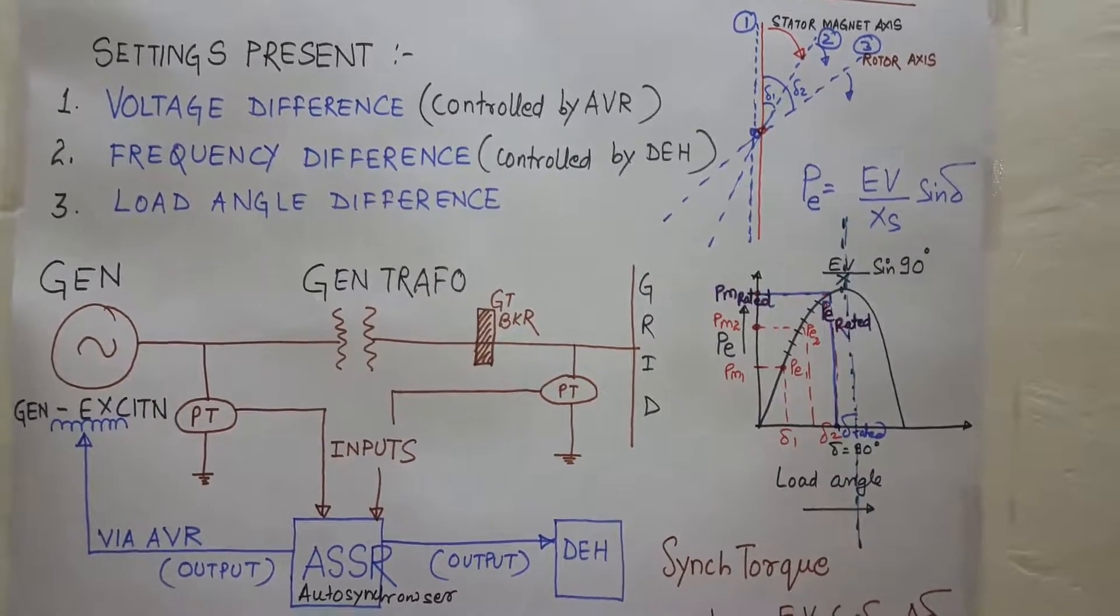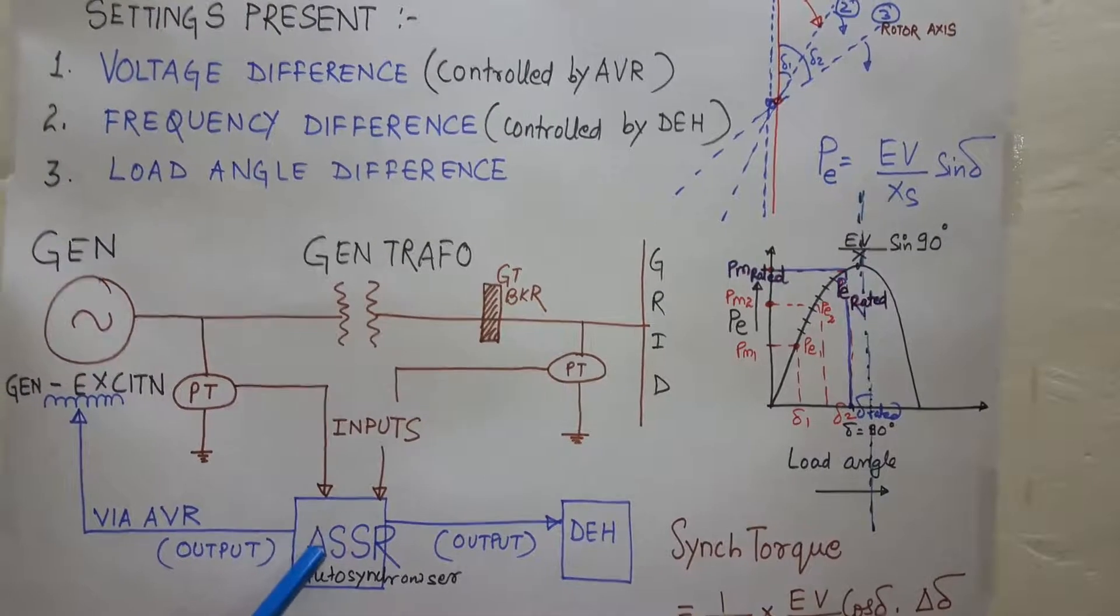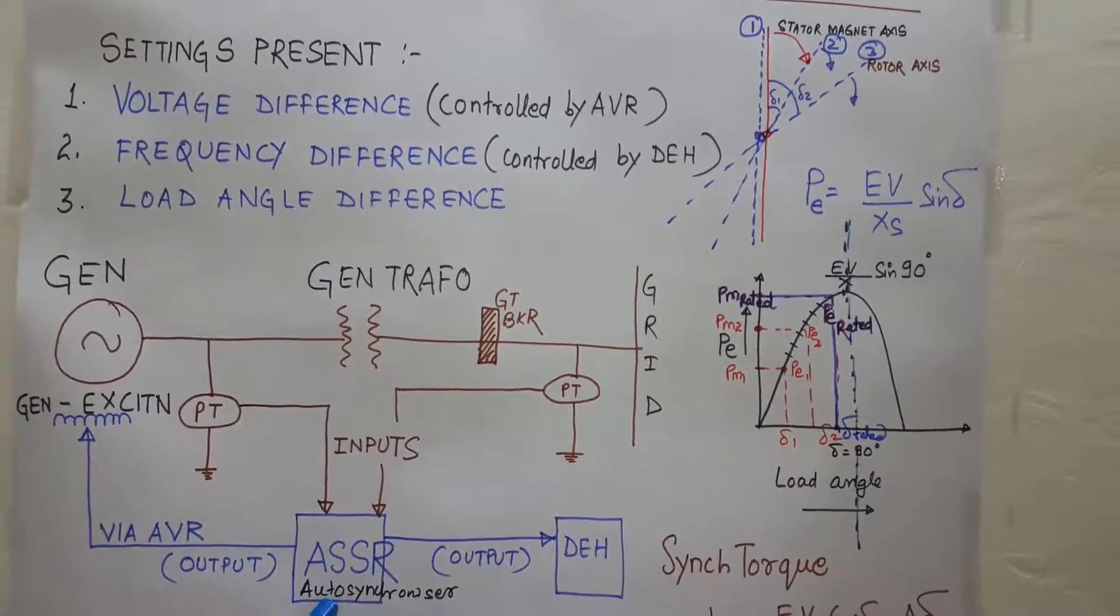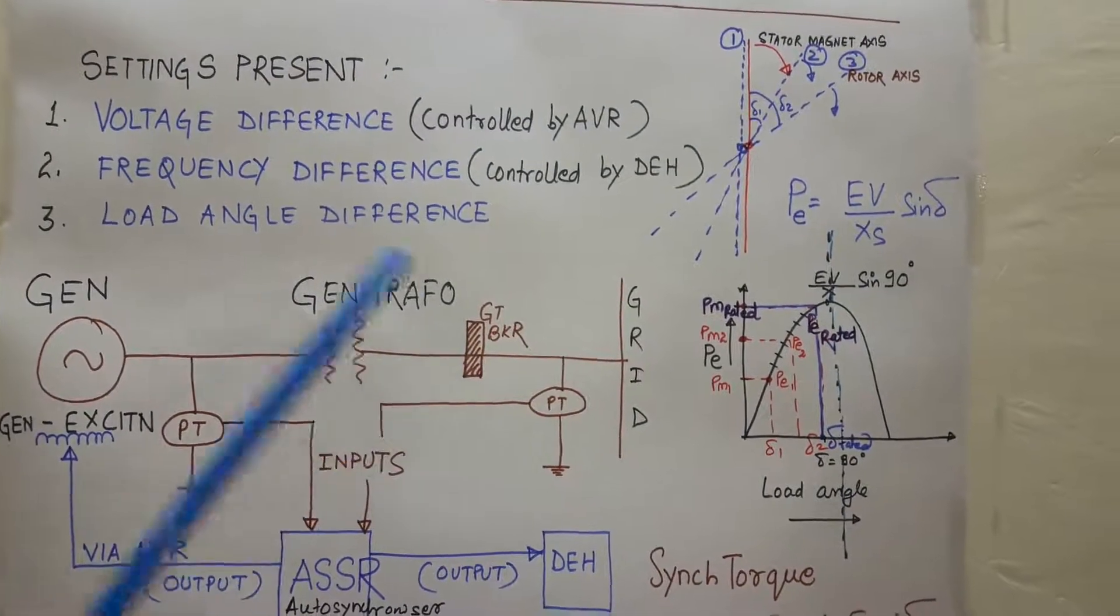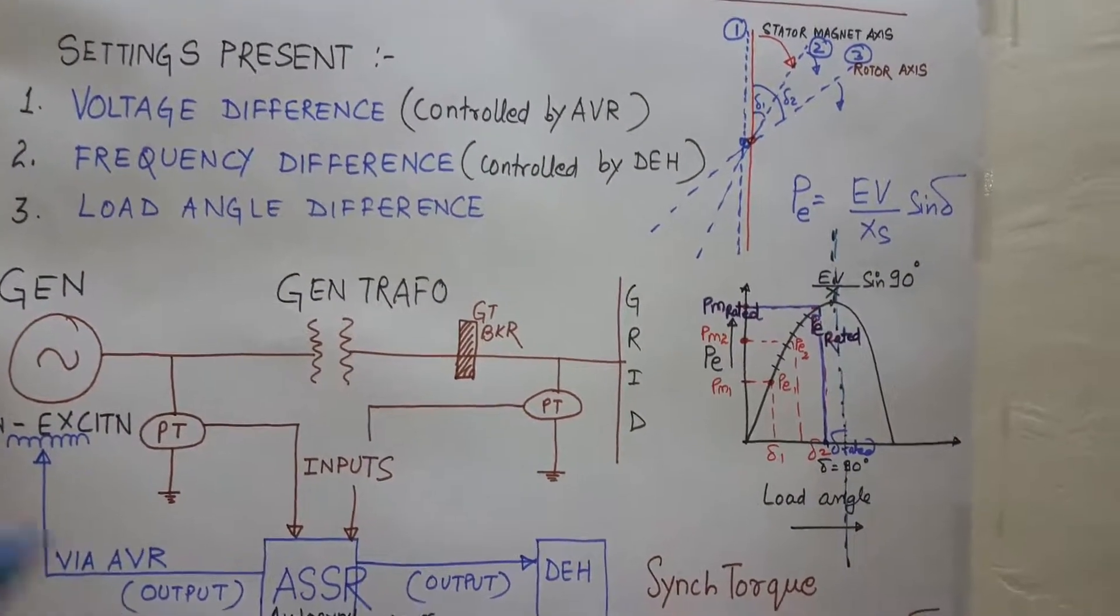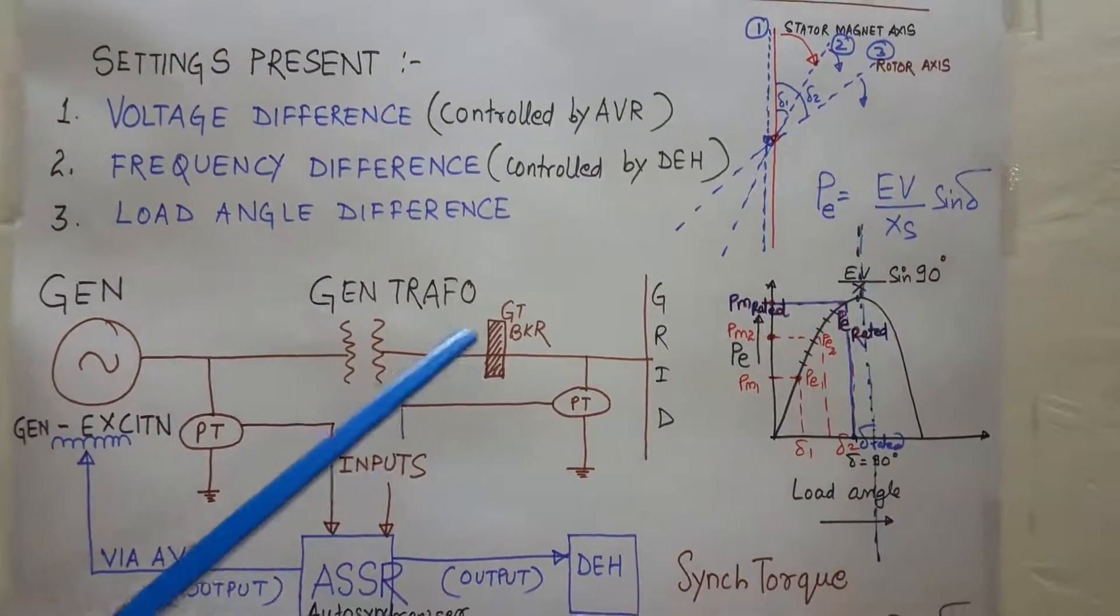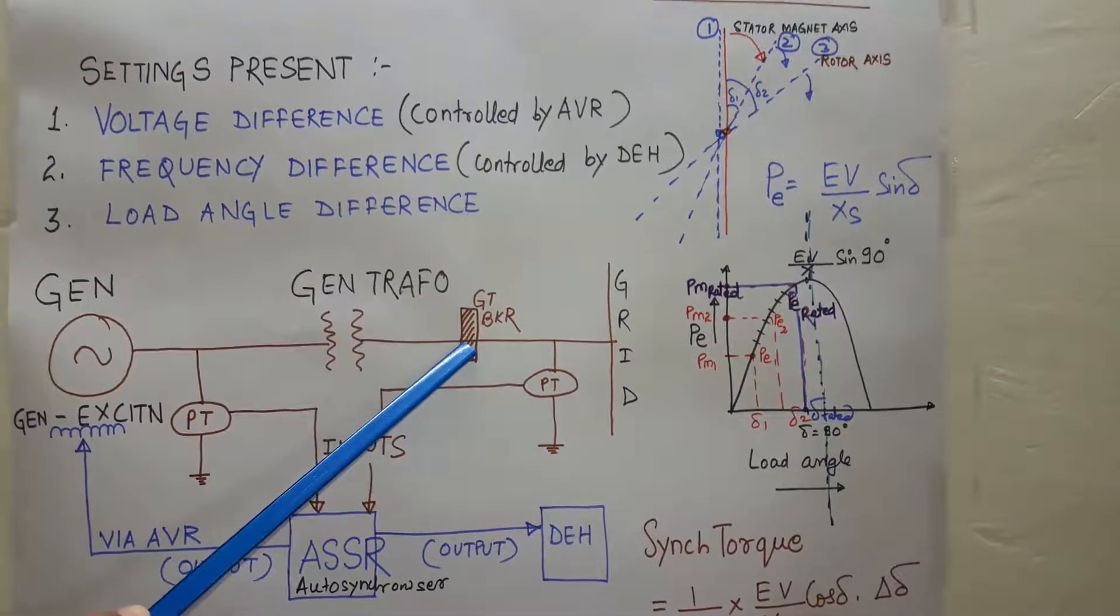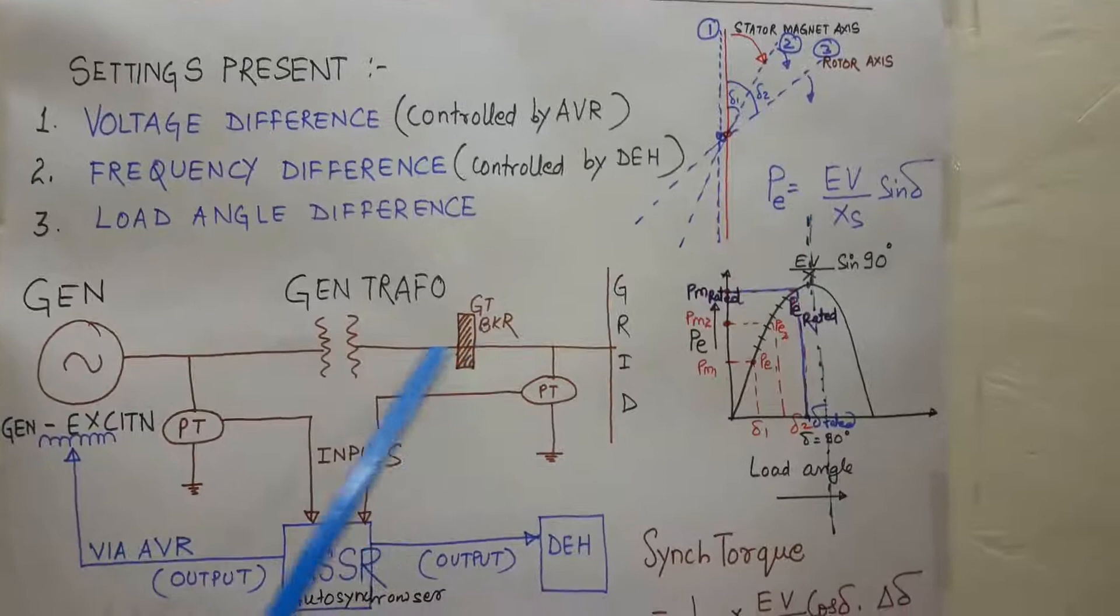Now auto synchronizer will go for synchronization. It will release one contact, and the contact is present in series with the closing circuit of the GT circuit breaker. So now the GT circuit breaker will get a close command and will close, and the generator will be synchronized with the grid by this GT breaker.